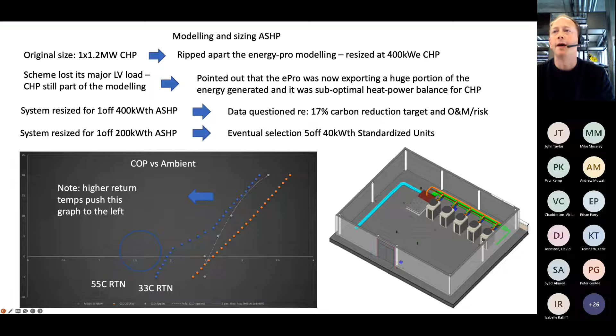a lot of the modelling that we get done, we have to make sure that we believe the data that's coming back, and a lot of the Energy Pro and TM46 stuff is a bit fuzzy, and it doesn't have real feedback from clients back to the consultants of whether or not that information is correct. The return temperature is a big issue for us, and it's rarely a consideration at the design stage, but it's something that everyone should think about. The energy sizing, the peak plant, again, they seem to be incentivized to oversize it, and the diversity curves are an example of that, and I'm really wary of that type of thing.